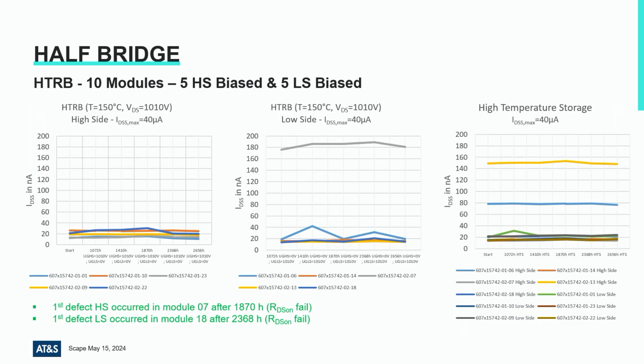We have HTRB on 10 modules, a half-bridge configuration tested up to 1,000 volts. We had the first failure on the high side on one module at 1,800 hours, and a first defect on another module at 2,300 hours, which is already quite promising. The test is still going.